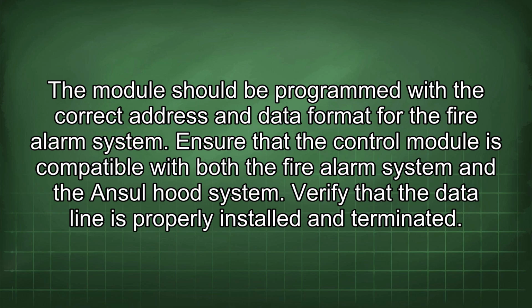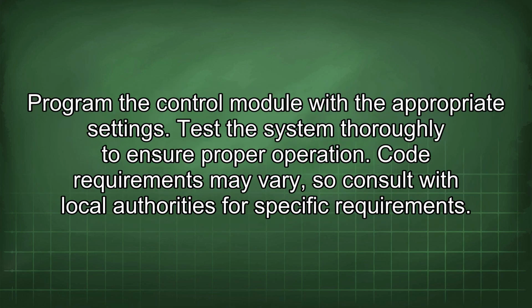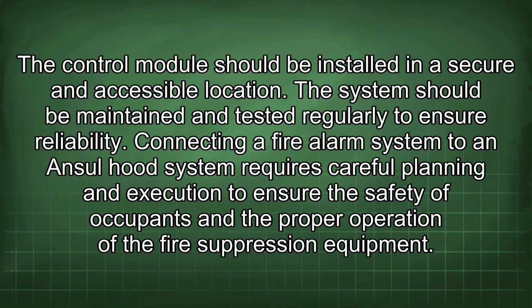Ensure that the control module is compatible with both the fire alarm system and the Ansul hood system. Verify that the data line is properly installed and terminated. Program the control module with the appropriate settings. Test the system thoroughly to ensure proper operation. Code requirements may vary, so consult with local authorities for specific requirements. The control module should be installed in a secure and accessible location. The system should be maintained and tested regularly to ensure reliability.